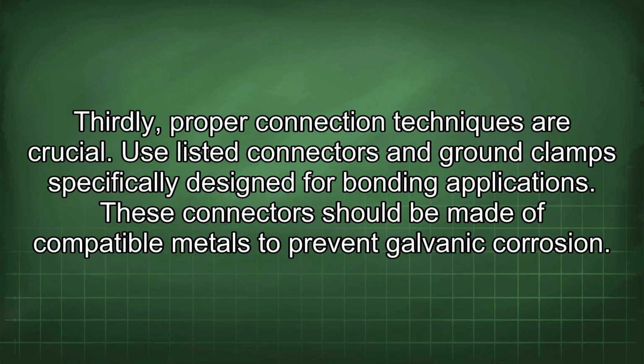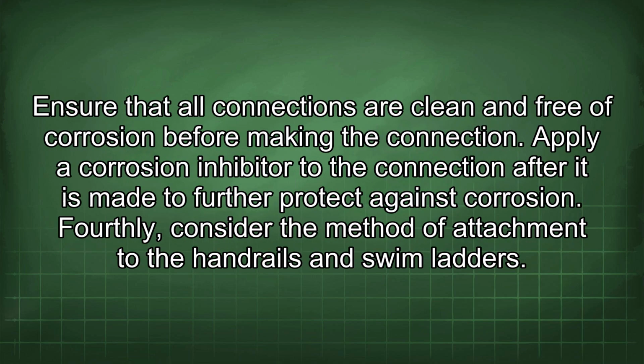Thirdly, proper connection techniques are crucial. Use listed connectors and ground clamps specifically designed for bonding applications. These connectors should be made of compatible metals to prevent galvanic corrosion. Ensure that all connections are clean and free of corrosion before making the connection. Apply a corrosion inhibitor to the connection after it is made to further protect against corrosion.